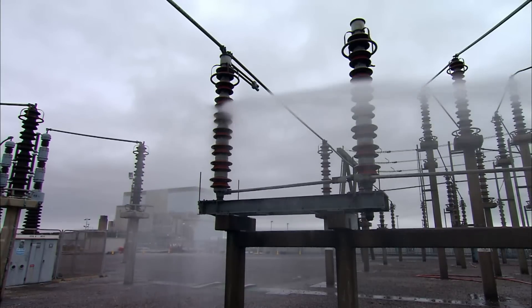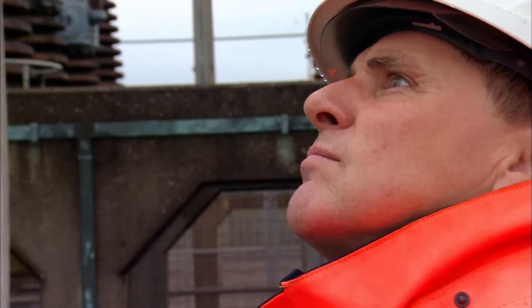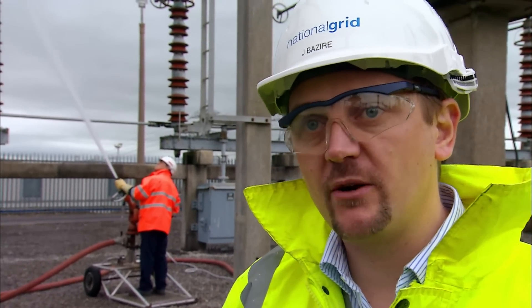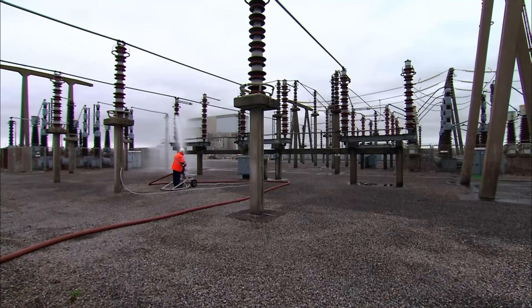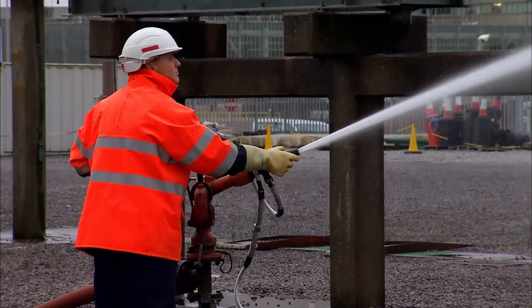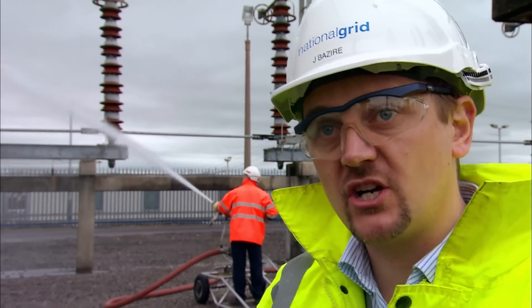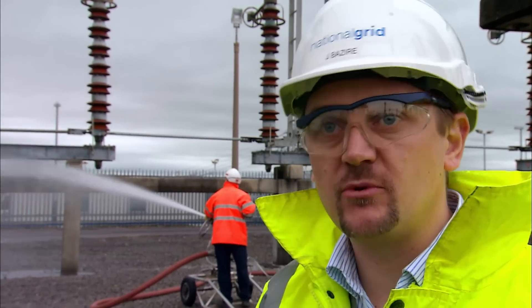The wash appears to be safely underway, but conditions can change unexpectedly. The conductivity of the water is constantly monitored. If the conductivity — meaning the purity of the water — falls below a certain level and becomes too conductive, the procedure stops. You have a 15-second time frame — you get an alarm, and then the pumps will shut down automatically. In addition, the pressure at which the water is delivered at 80 PSI must be maintained. If that drops off, the whole system will shut down.